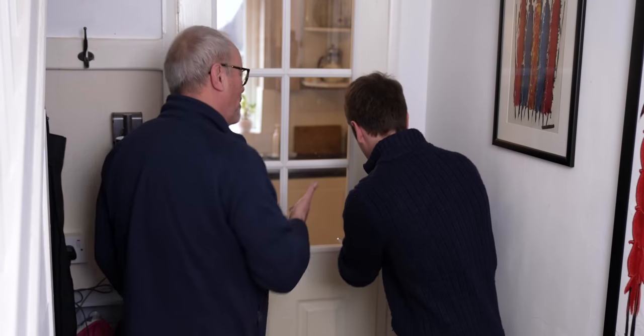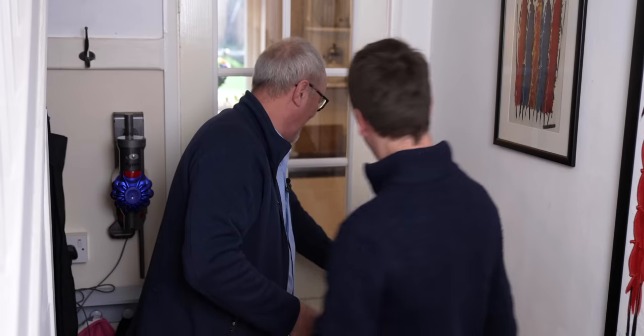I'm not feeling anything yet — other than I can hear the noise. The way we find out precisely where the leaks are coming from is to close all the doors in the house while the fan's running, and open the doors one at a time. You feel the pressure? Oh my God. That's not like a slight leak — that's wind coming through here. Yeah, so that wind's got to come from something. And it's cold. That is amazing — that isn't a little bit of air, that's a lot. So we've identified there are some big holes somewhere in the kitchen.